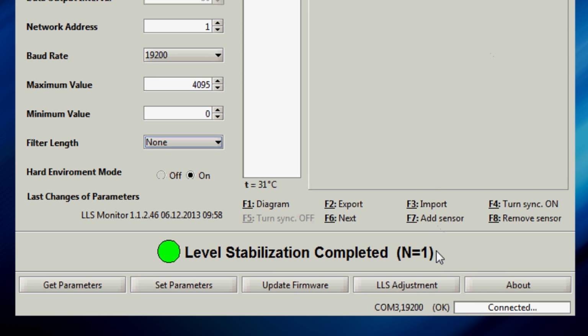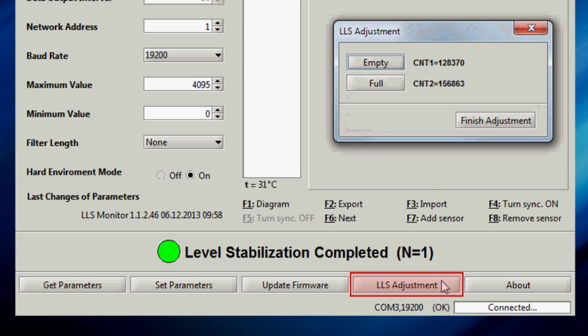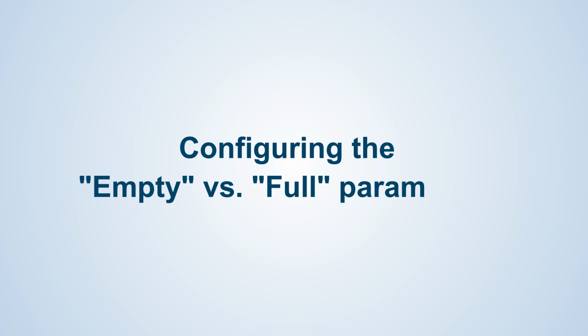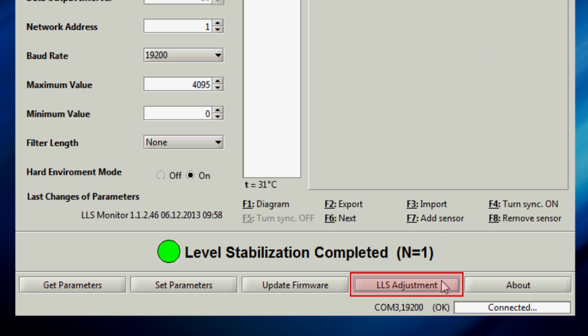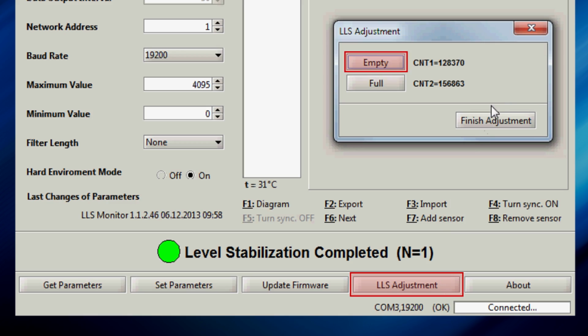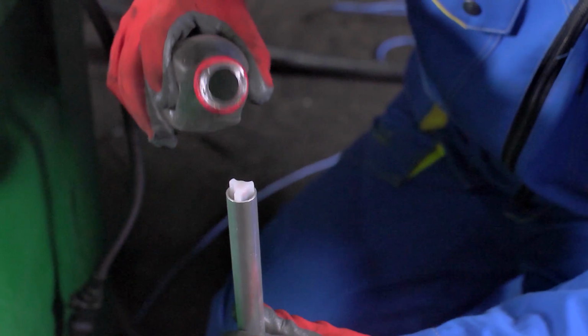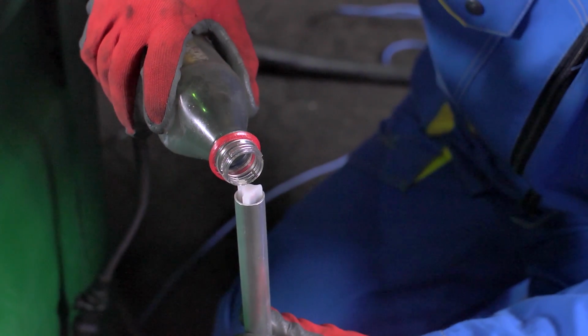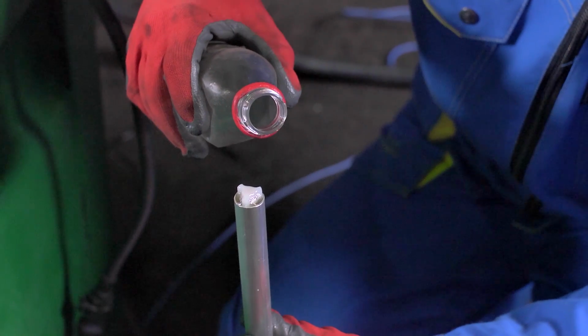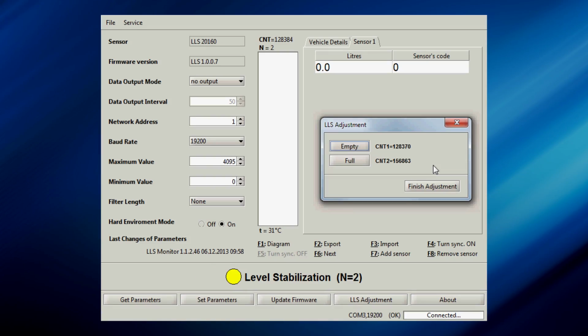Next, click the LLS adjustment button and proceed to the empty full setting. Now proceed to calibrate the sensor, which involves configuring the full versus empty parameters. Here is one of the possible ways to configure the full versus empty parameters. Fill the sensor probe with the type of fuel in which the sensor will be used. Another way is to immerse the sensor into a calibration tube filled with fuel.